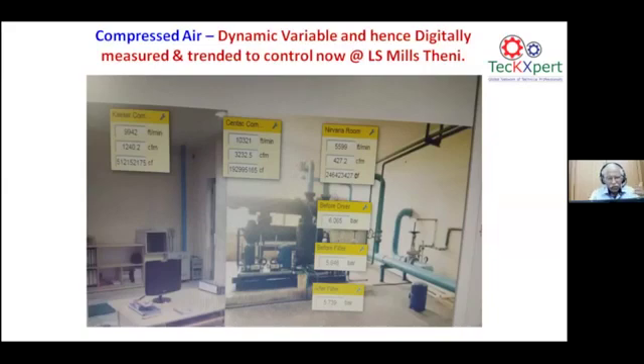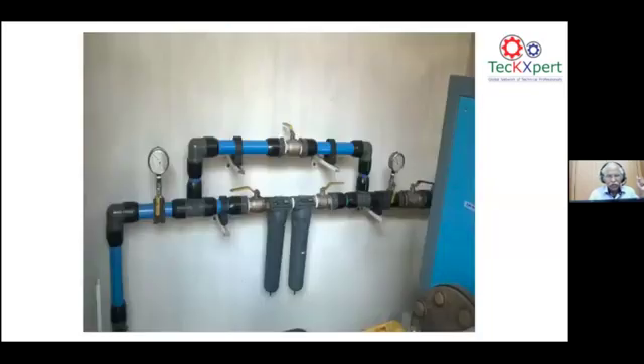And at the same time, what is there before the dryer, after the dryer, and after the receiver? Everything is monitored. I don't say we have to go for such a sophisticated, costly system, but definitely pressure differential gauges across the dryers will show if the dryer is the culprit with more pressure drop, and what the loss is in the existing dryers, especially the refrigeration dryers. This is an economical way of doing it.